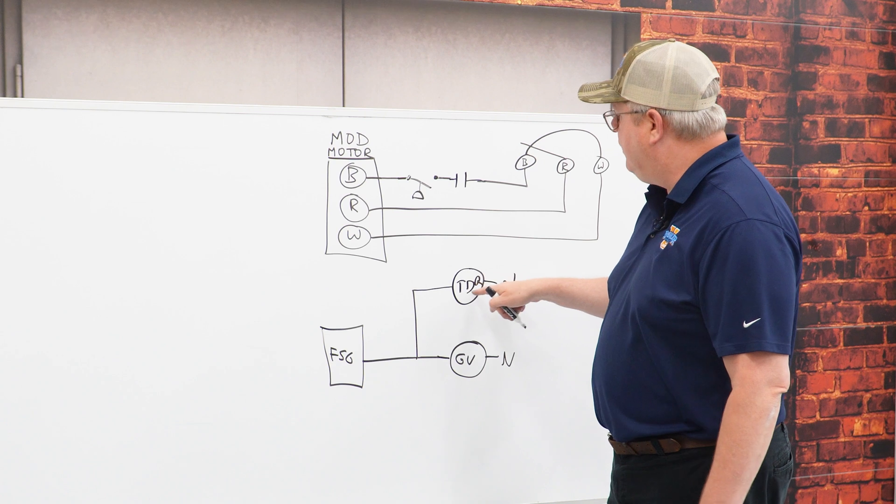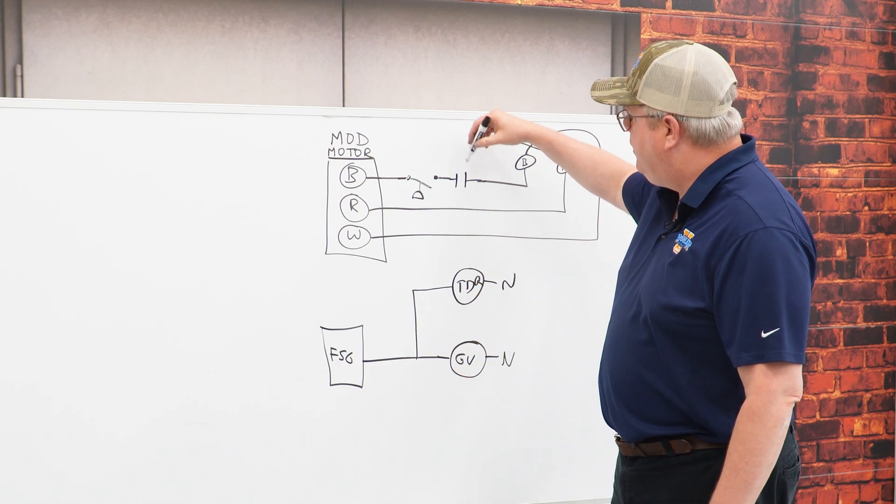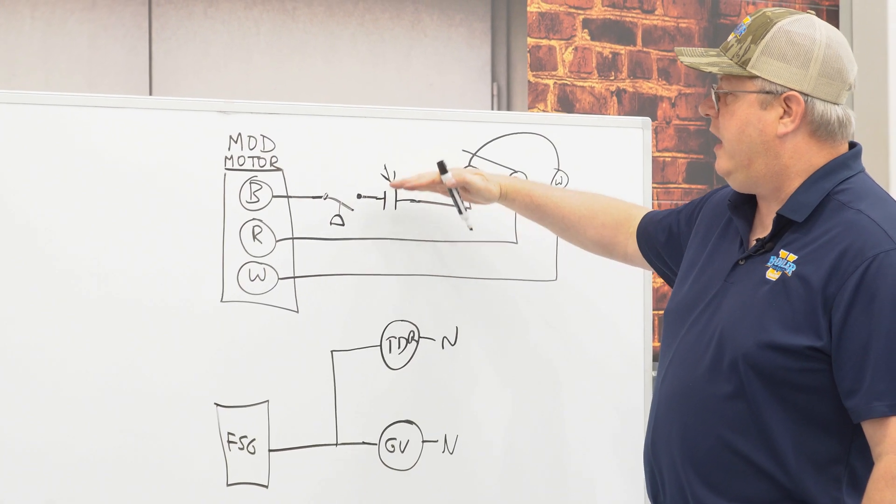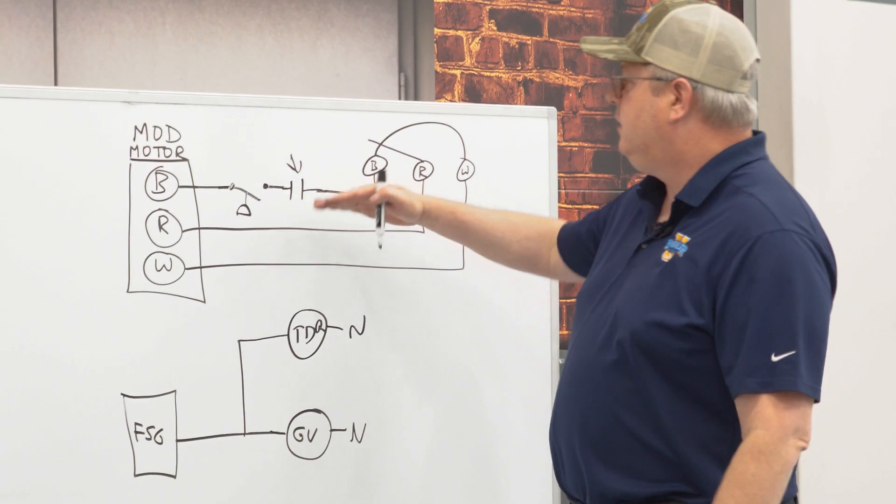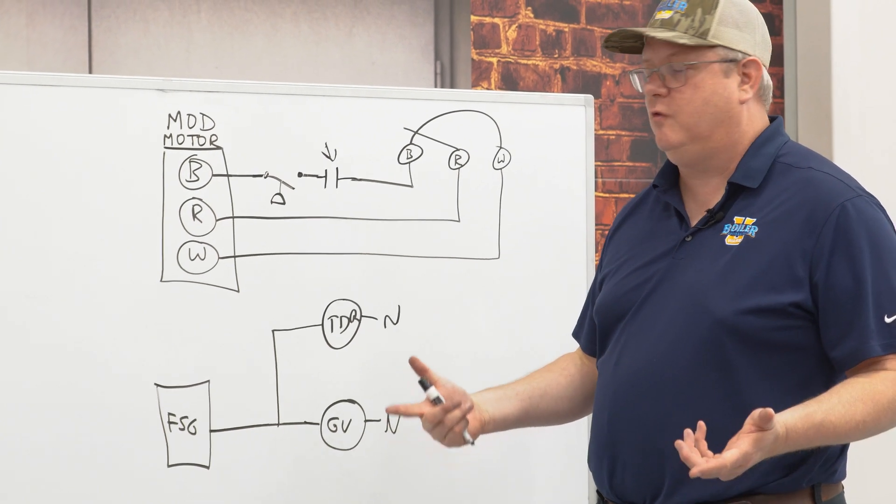So we've got a time delay relay down here, and when our flame safeguard energizes our gas valve, then we'll have a delay here—two minutes, five minutes, whatever that duration is—to prevent it from coming out of low fire. So that's going to inhibit its tendency to short cycle.